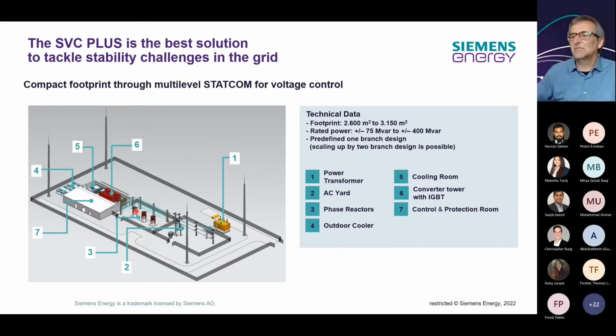We have the building. We can see the converter itself here with the IGBTs. The IGBTs, they're all water cooled. So there is a cooling system here to bring the cooling water to the IGBTs. There's the outdoor cooler. There's the heat exchanger. And of course, there's the control room, which takes care of the control of the system with the protection equipment, with the SCADA system, whatever is needed to remotely operate such a STATCOM. Of course, it is an unmanned station.